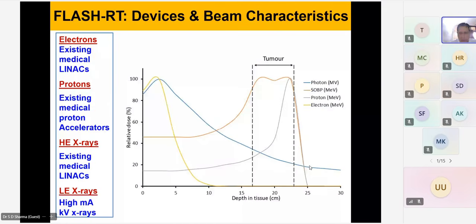Now, if we generalize this, flash radiotherapy can be delivered by what type of system and what type of beam. In general, we can say electrons have the capability, protons have the capability, high energy X-rays have the capability, even low energy X-rays at higher dose rates have the capability. Now you can see the dose distribution of all these. If I talk about electrons, and their energy is limited, maybe 6 MeV or 10 MeV, they will have limited penetration. Higher energy X-rays will have higher penetration. For the proton beam, we have to generate an SOBP, that is a spread out Bragg peak. I think Dr. Lalit will discuss this in detail later on. Depending on their energy, you can treat either superficial or deep-seated tumors by proton.